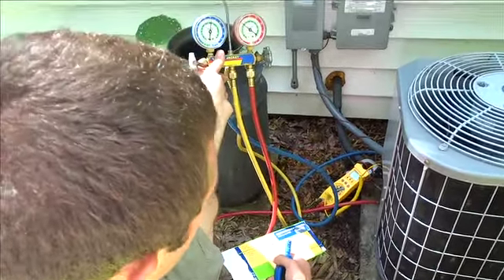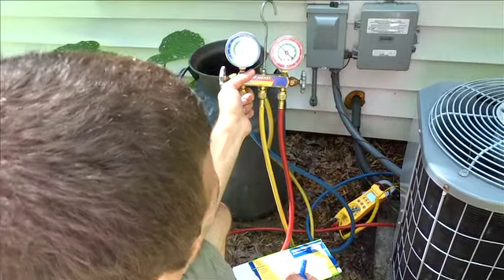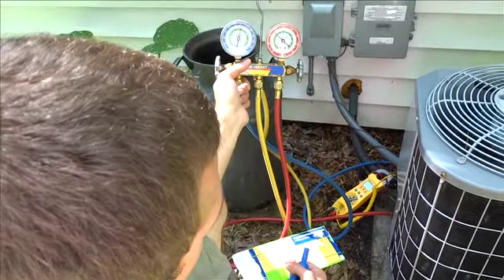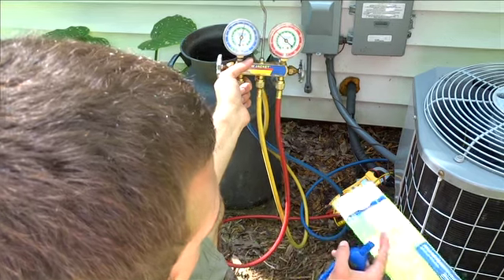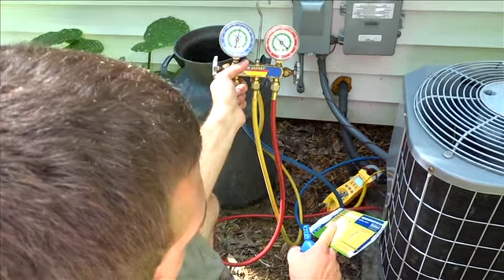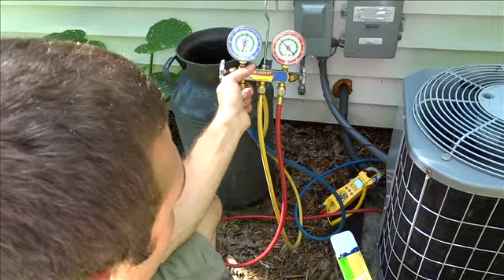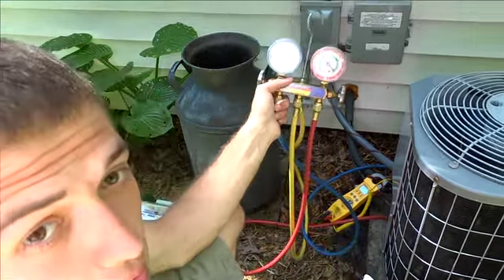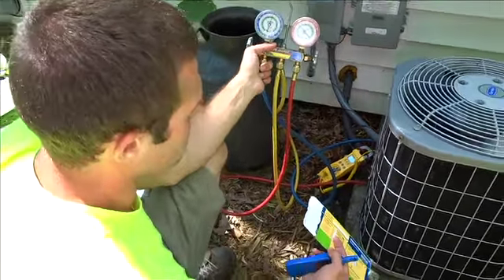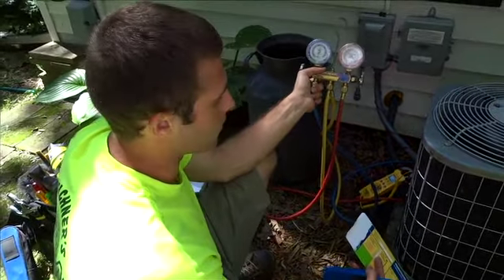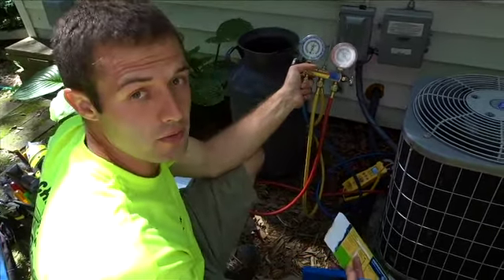Right now it's at 62 degrees and 35, which is, according to this, to get a lower line temperature, you have to add refrigerant. So according to the readings right now, we're a little low on refrigerant. The unit may still be working, but once it's properly charged, it just works more efficiently.